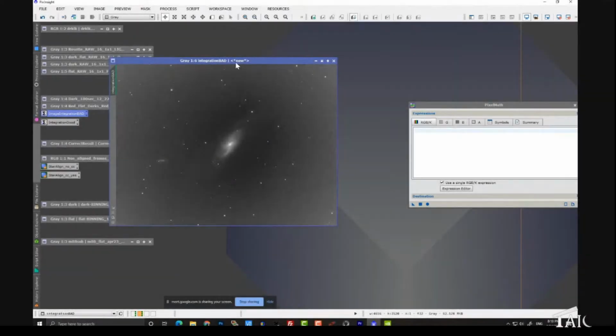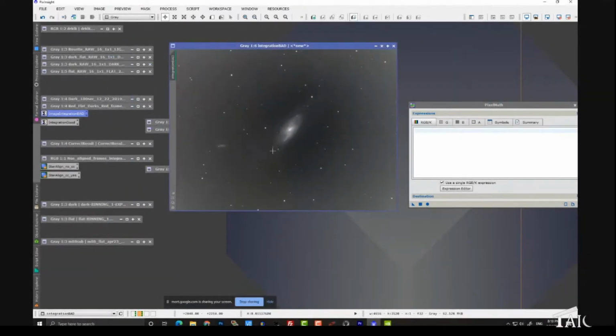So this image processor, and this is so common, had this problem where the flat field image looked like it was either over or under correcting. And this is the look that you get. You can totally guess what's going on anytime you get this kind of look.